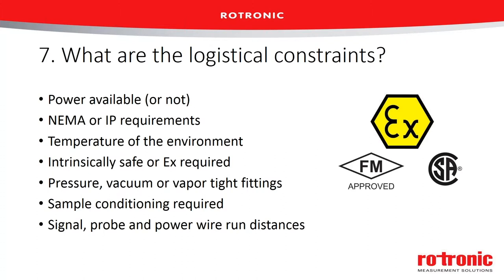For pressurized or vacuum-based systems, the sensor may need to go through a fitting — it's important that the sensor seals off well, both on the outside edges and down the length of the probe, so pressure isn't lost or air isn't allowed in. Sample conditioning may also require additional hardware. For signal and probe power over long distances, if you have an analog output and know you need to run the signal a long distance, avoid a 0–10 volt output — the wire resistance will affect readings. It's better to choose an instrument with a 4–20 milliamp output.